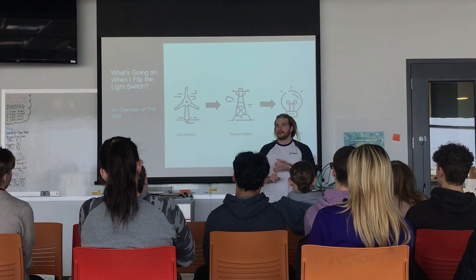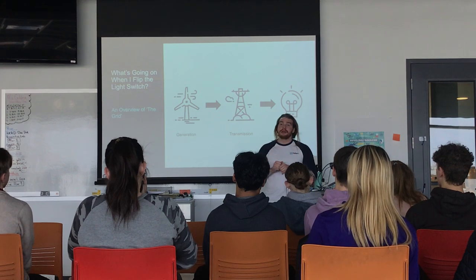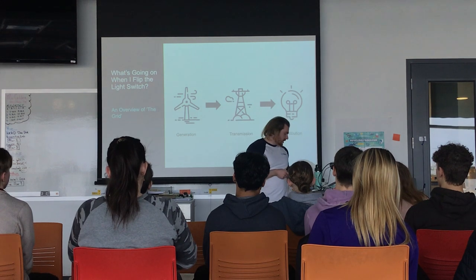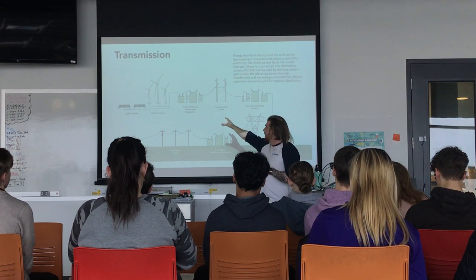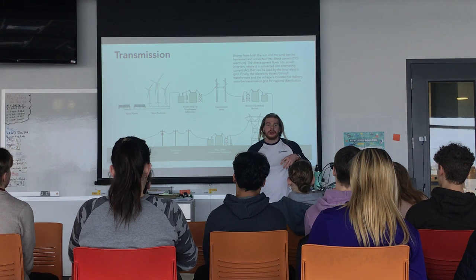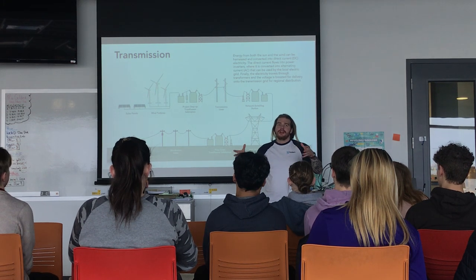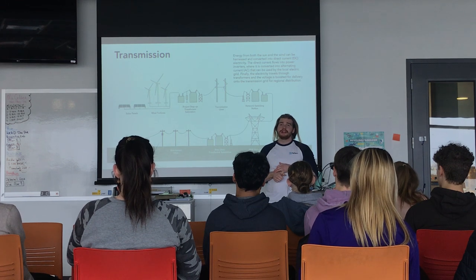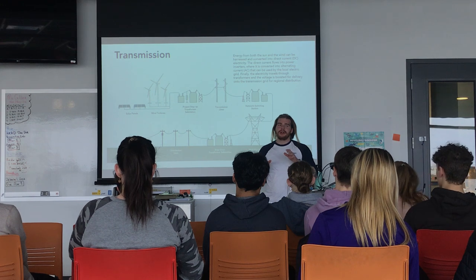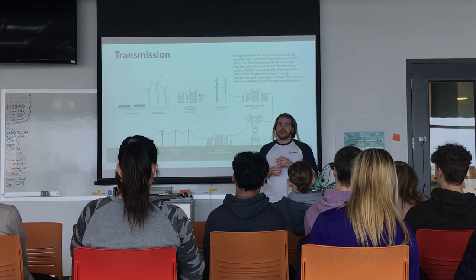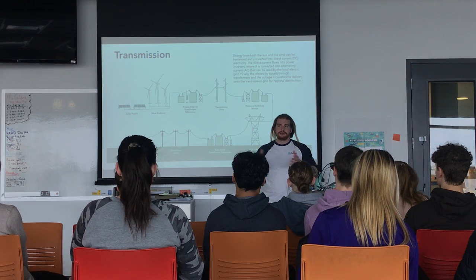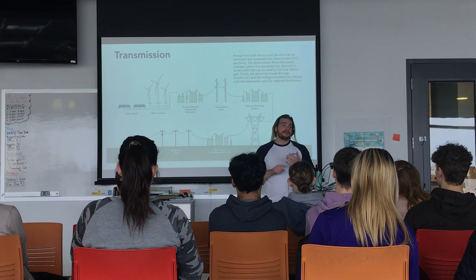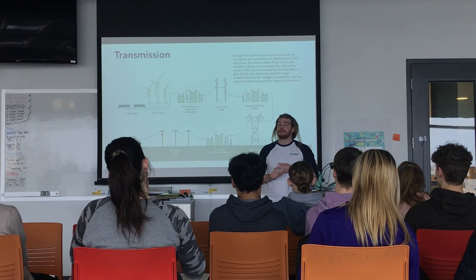Generation is all the points where energy is produced—whether that's a coal plant, a wind turbine, a solar panel, a nuclear plant, whatever it is. Transmission is about long-distance, ultra-high voltage transmission of energy. We produce the energy and it goes to substations that step up the voltage—they raise the voltage and lower the current. The reason we run electricity at high voltage across long distances is because high voltage, low current means you lose less energy to resistance, making it much more efficient for long-distance transmission, though it is very dangerous for actual usage—we're talking 500,000 volts.